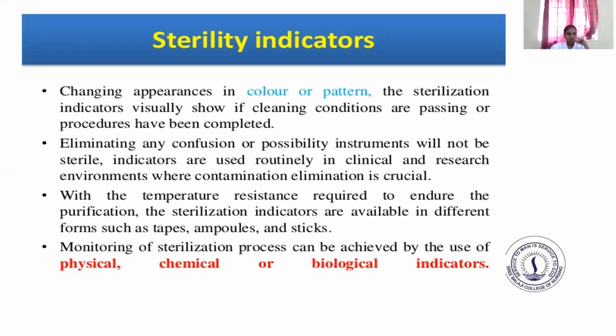Sterility indicators. Changing appearance in color or pattern, the sterilization indicators visually show if cleaning conditions are passing or procedures have been completed, eliminating any confusion or possibility instruments will not be sterile. Indicators are used routinely in clinical and research environments where contamination elimination is crucial. With the temperature resistance required to endure the purification, the sterilization indicators are available in different forms such as tapes, ampoules, and then sticks. Monitoring of sterilization process can be achieved by the use of physical, chemical, or biological indicators.